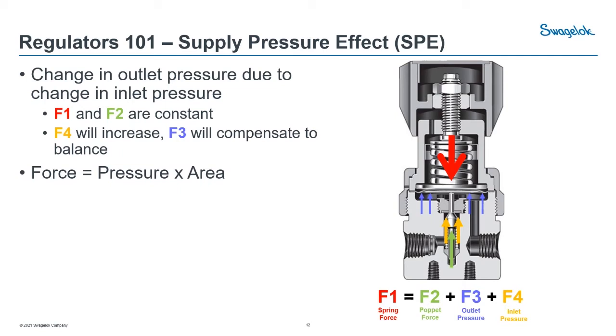Next we'll talk about supply pressure effect. This is something you might have heard of, and it tends to be very common in gas cylinder applications where you'll see your outlet pressure change. Supply pressure effect is that change in your outlet pressure due to a change in your inlet pressure. Going back to our balance of forces, F1 and F2 are constant — we've set our range spring and our poppet force is already selected. So we're left with F4 and F3. If we increase F4, we tend to decrease F3; if we decrease F4, our outlet pressure will increase.